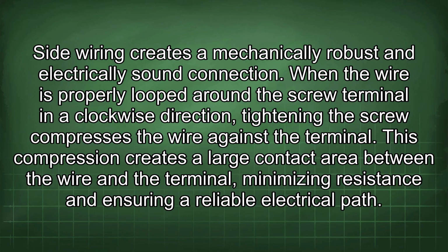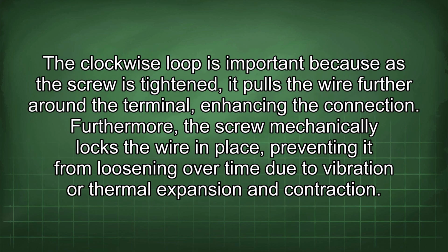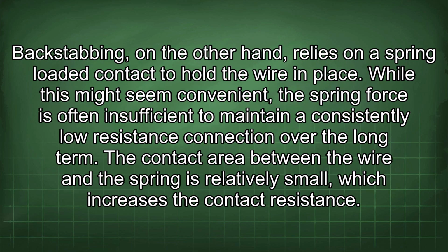Side wiring creates a mechanically robust and electrically sound connection. When the wire is properly looped around the screw terminal in a clockwise direction, tightening the screw compresses the wire against the terminal. This compression creates a large contact area between the wire and the terminal, minimizing resistance and ensuring a reliable electrical path. The clockwise loop is important because as the screw is tightened, it pulls the wire further around the terminal, enhancing the connection. Furthermore, the screw mechanically locks the wire in place, preventing it from loosening over time due to vibration or thermal expansion and contraction. Backstabbing, on the other hand, relies on a spring-loaded contact to hold the wire in place.